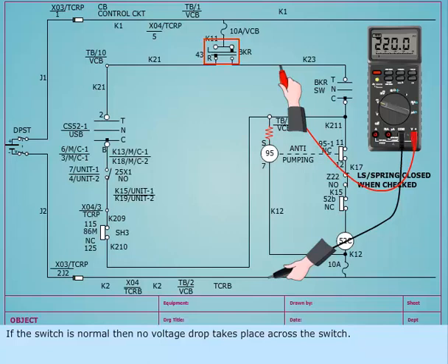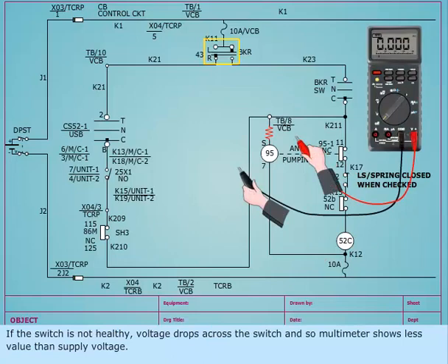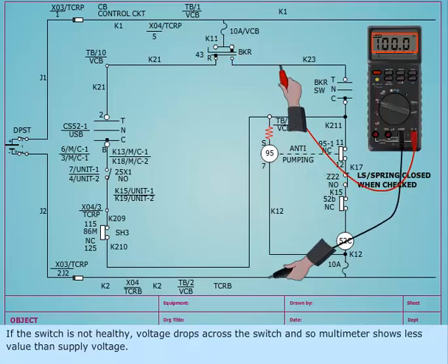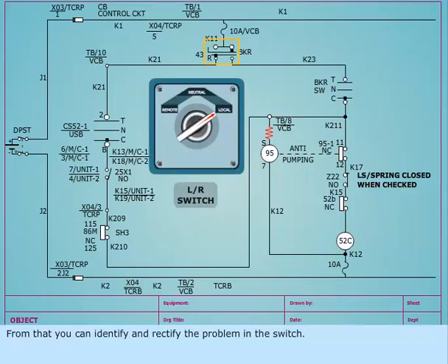If the switch is normal, then no voltage drop takes place across the switch. Hence the multimeter shows full supply value. If the switch is not healthy, voltage drops across the switch and the multimeter shows less value than supply voltage. From that you can identify and rectify the problem in the switch.